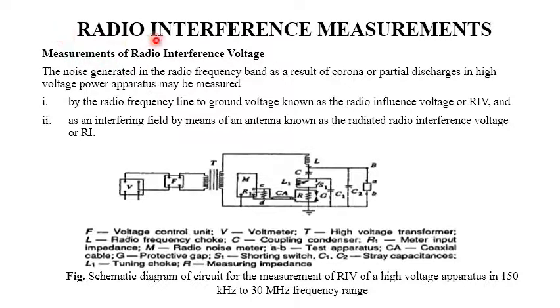Next concept is radio interference measurement. In many electrical apparatus like transformers, line conductors, and rotating machines will produce unwanted electrical signals in the radio and high frequency devices like television band, microwaves, etc. These signals arise due to corona discharge in the air, internal or partial discharges in the insulation, sparking at the commutators and the brush gear in the rotating machines, etc.